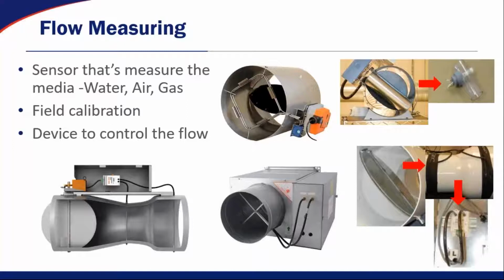Typically, they have some level of field calibration associated with them. So once they get installed in the ductwork, whatever conditions are going on inside the ductwork have to be accommodated for. So again, going back to if you have a bunch of elbows in the ductwork, you have to accommodate for that. If you have a lot of pressure drop after that airflow control device, you have to accommodate for that, and you basically tune it in the field using a K factor, which is setting it to the best condition you can while it's installed in the field.